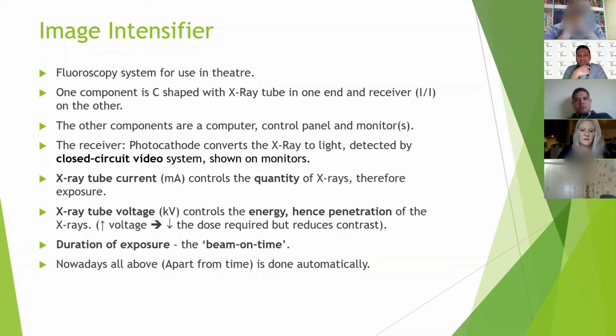There are factors that would affect the quality of the image, and these you need to know about: the current, the voltage, and the exposure time, and how they affect the image you get. The current, which is measured in milliamperes, controls the quantity of the radiation, the number of rays that you are getting. The more rays you have, the better the quality of your image.